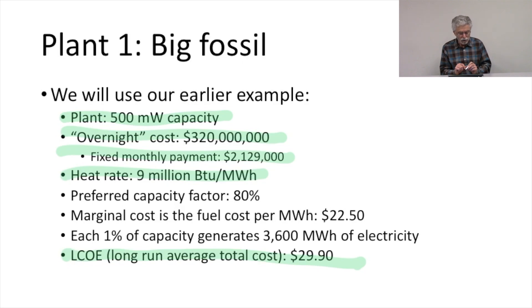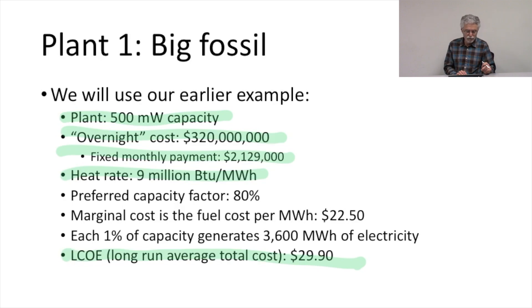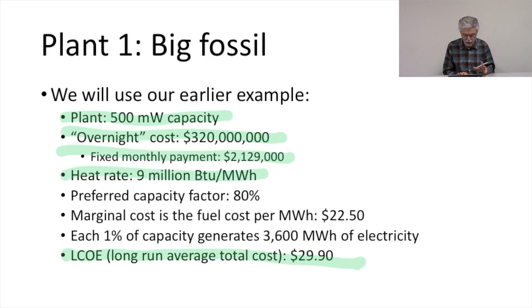The marginal cost is the fuel cost per megawatt hour, and that's $22.50. We just take our fuel cost and our heat rate and we get $22.50 per megawatt hour. Each 1% of capacity of this power plant will generate 3,600 megawatt hours of electricity.